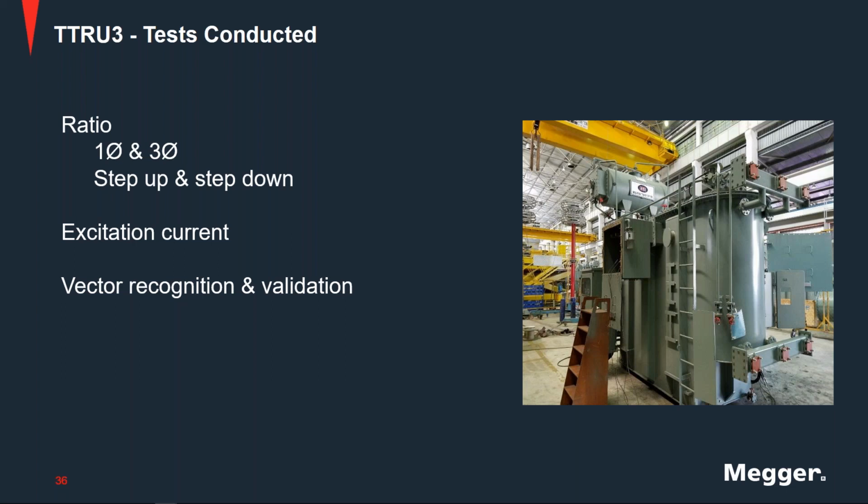You need to make sure that you have the correct vector transformer configuration when you're doing your testing, because if you were to put a transformer with an incorrect vector into service on a system that was expecting a different configuration, you could have catastrophic failures.